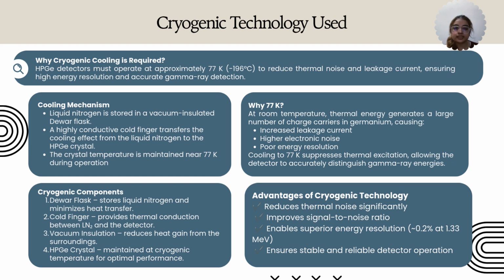The cooling is then transferred to the HPGE crystal through the highly conductive component called a cold finger. By maintaining the crystal at cryogenic temperature, thermal excitation is significantly reduced, resulting in lower noise level, improved signal-to-noise ratio, and much better energy resolution. Therefore, cryogenic cooling is a critical technology that enables HPGE detectors to perform precisely in gamma ray spectroscopy.